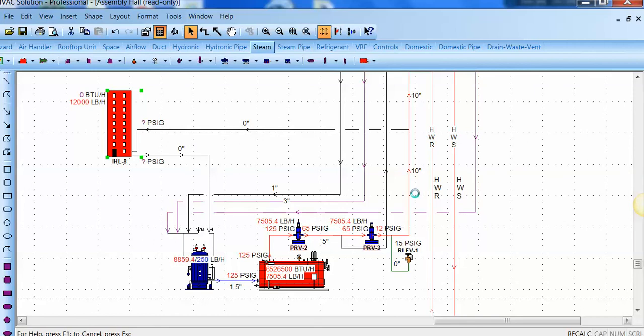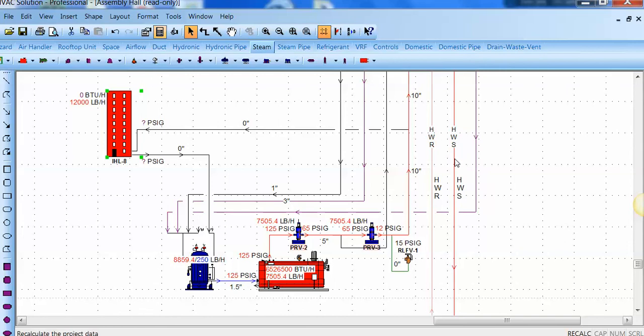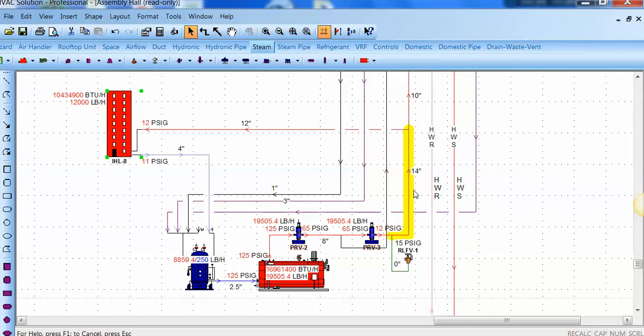And watch what happens to the 10-inch pipe. So it's running thousands of calculations. It's checking the entire system and rerunning the calculations. And when it drills back down to the mechanical room, you can see the main has gone from 10 inches to 14 inches.